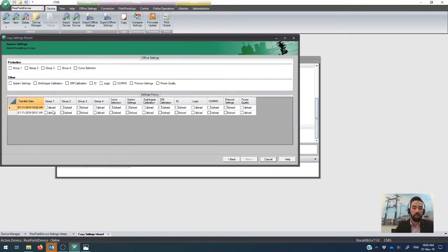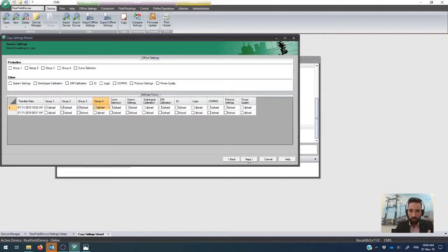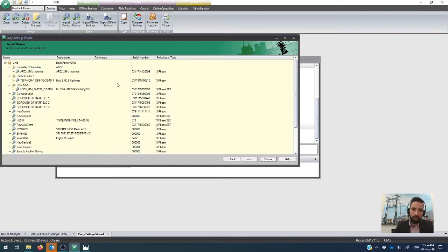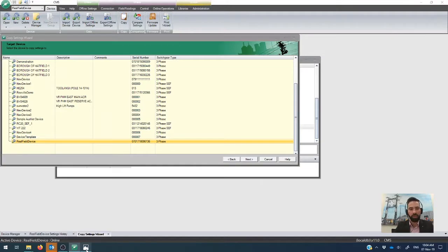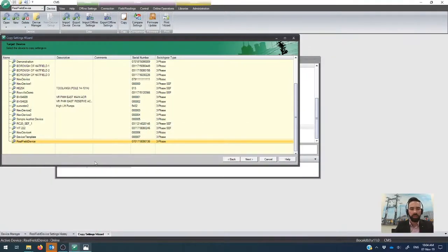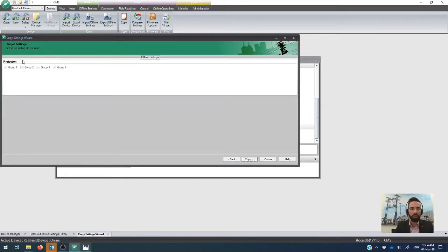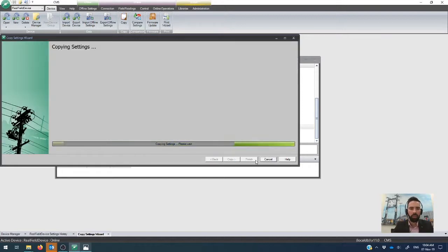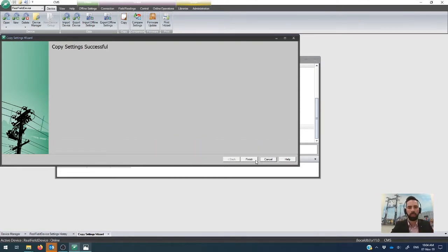Or alternatively, in this case, what we want to do is take the most recent uploaded settings. I'm just going to take the group settings here just for simplicity. We pick next, and we copy it into the same device file, so into the same zone here. The only difference is that this time around, we're going to copy it onto the offline settings. And because I picked all the groups, it automatically picked it across. We go copy, and that is then copying the settings and overriding what's in the offline settings. So that's done.